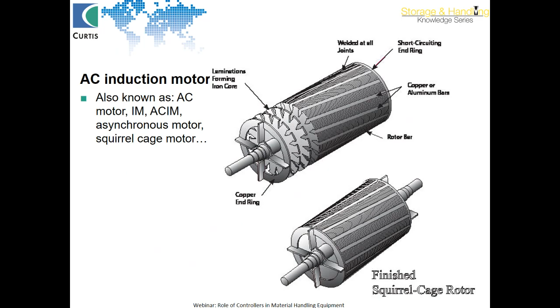It is basically a laminated iron core with copper or aluminum bars, which are short-circuited at the end by the end rings. Aluminum bars are most commonly used because of the cost effectiveness they offer. But there are certain applications in which even copper bars are used, where very high efficiency and lower losses are required. They are called AC motors, typically AC induction motors, asynchronous motors, or squirrel cage motors. They are referred to by different names in the industry.